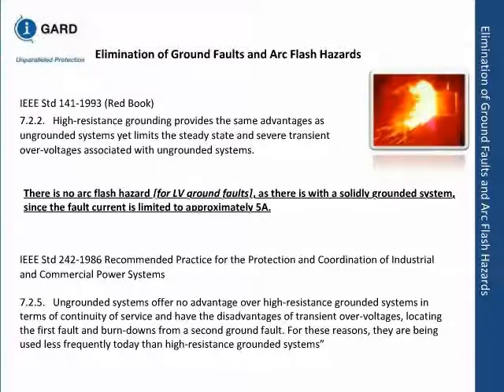Since 95% of the faults originate as ground faults, if you can remove that before the second happens, you do not have an arc flash problem. Under it you see recommended practice for protection and coordination. It came from the Buff Book. Look very clearly at what it says: ungrounded systems offered no advantage over high-resistance grounding systems in continuity of service, and they have the disadvantage of transient overvoltage. Now you can see that 141 and 242 basically say the same thing. IEEE realized it too, and we are trying to incorporate everything in one standard.